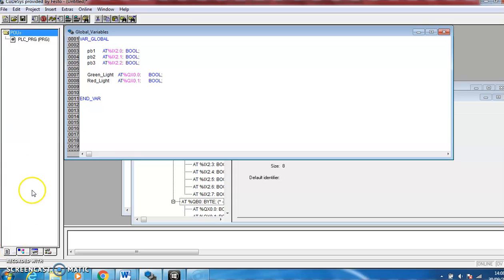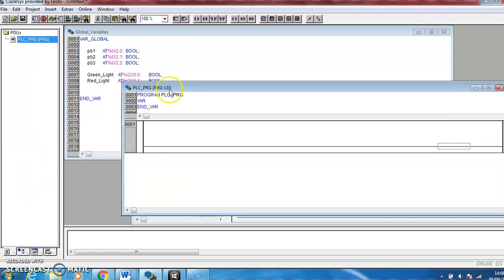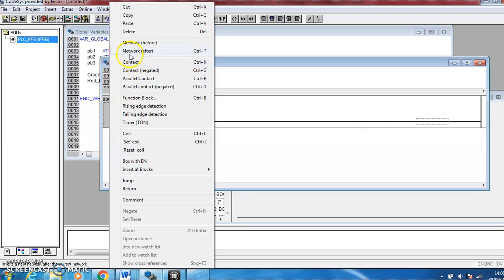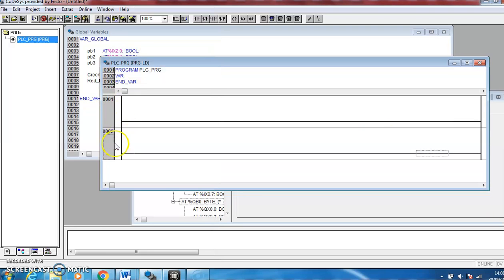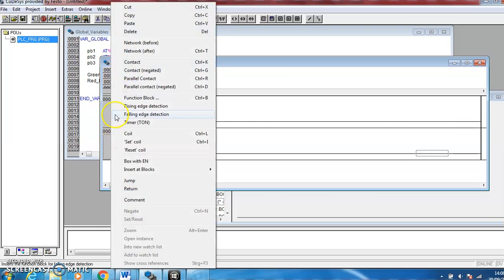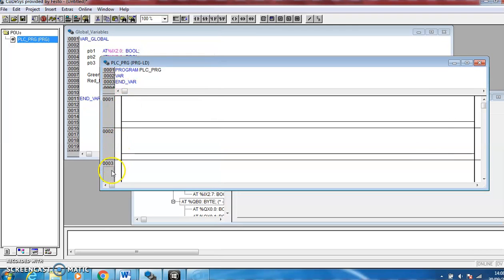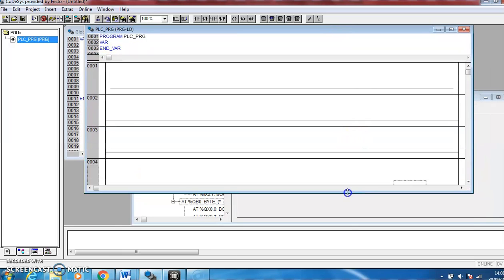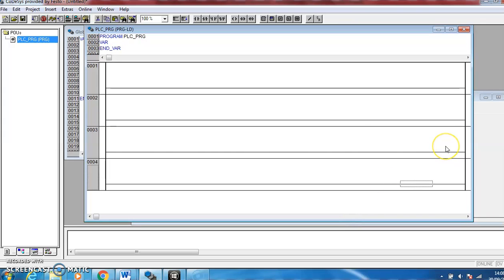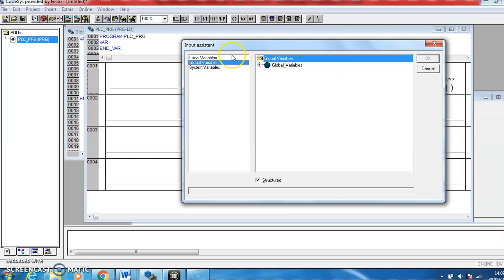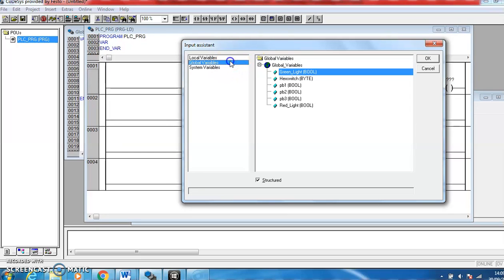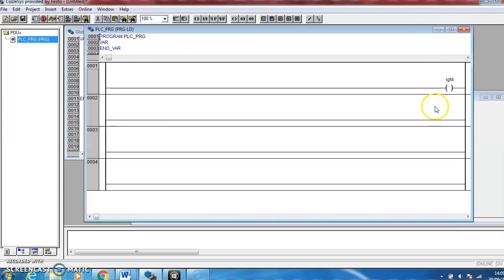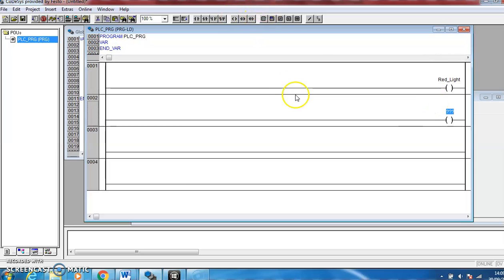So if we go back to the program then, we can start the program. So in ladder, the key is I'm just going to add networks here. If I left click into that gray area then right click, I can add a few networks. The key to basic ladder diagrams is only have one output, one line of code for each output. So I'm just going to put on my outputs, the red light and the green light.